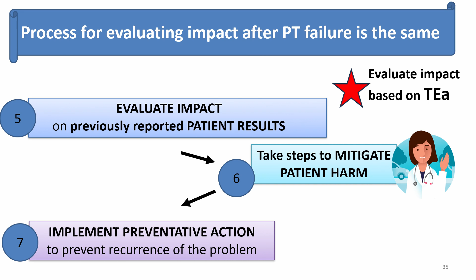So the last step of the process for recovery from an out-of-control condition or PT failure is to implement preventative action. So frequently, part of the preventative action is to redesign your QC program to identify the out-of-control condition more quickly, or if you're not getting the appropriate alerts, to get the QC alert when you have an out-of-control condition. To redesign the QC program, you can increase frequency of QC analysis. You can change the QC target mean or target standard deviations. You can add additional levels of QC materials. All of these will help improve the sensitivity of your QC program.